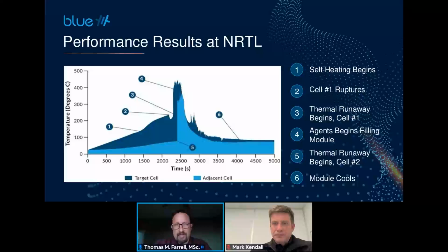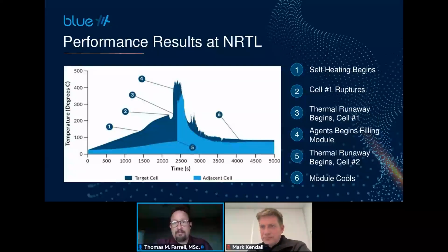And as blue was beginning to fill that module and start controlling that thermal runaway process, another cell immediately adjacent went into thermal runaway, and that's where you see at marker 5. Notice its temperature didn't reach as high as the core temperature on that first cell that we initiated. But both of them, once the module was filled with blue, those temperatures began to fall. Now, after that, there were a few more cells that went into thermal runaway. But after a little bit of time, you can see, out there at marker 6, there are no more thermal events, and it started to cool and continued to cool from there.